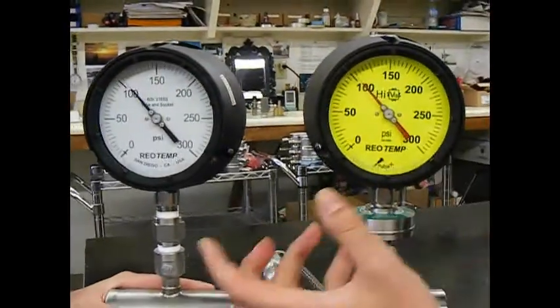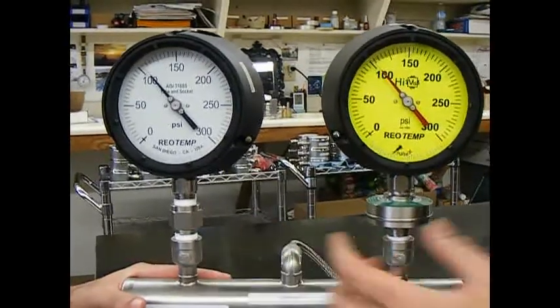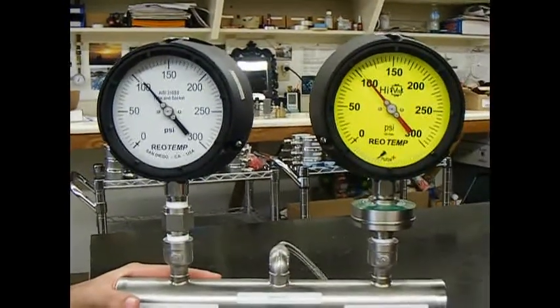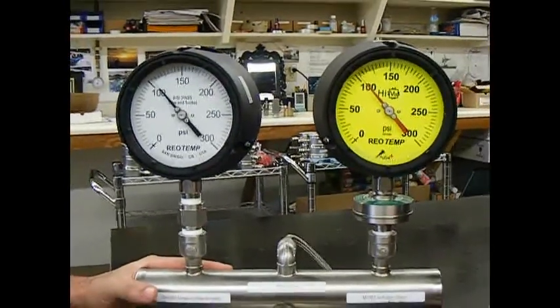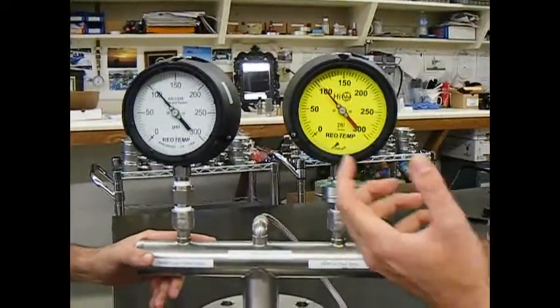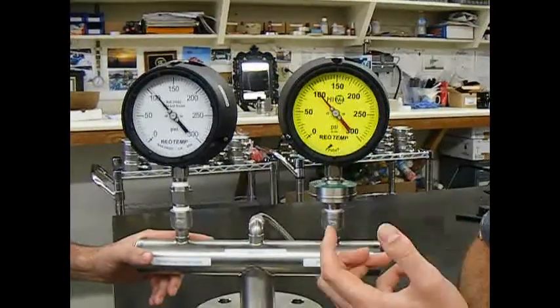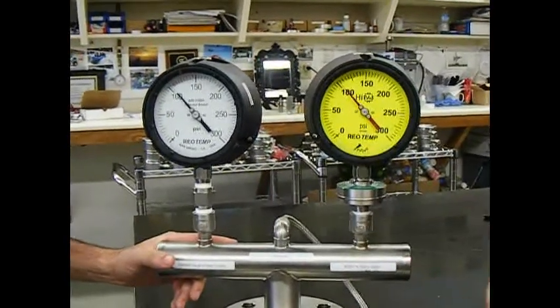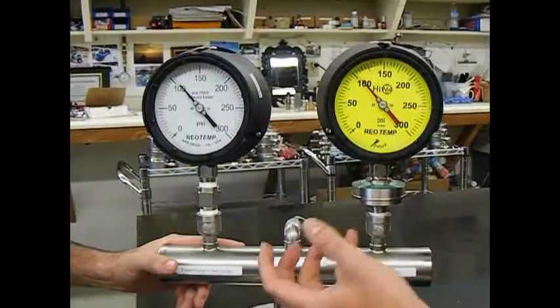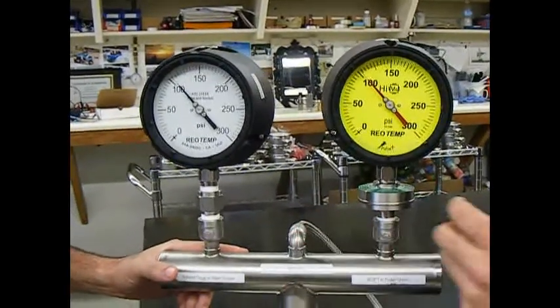What you're seeing here is the unit on the left, which is a standard process gauge with a water snubber. Snubbers are commonly used in the industry to slow down the process before it gets inside the gauge, but as you see here, a water snubber just doesn't do a good enough job in slowing down the process medium before it gets into the gauge.